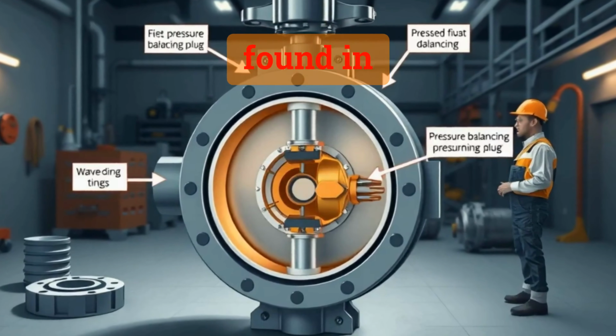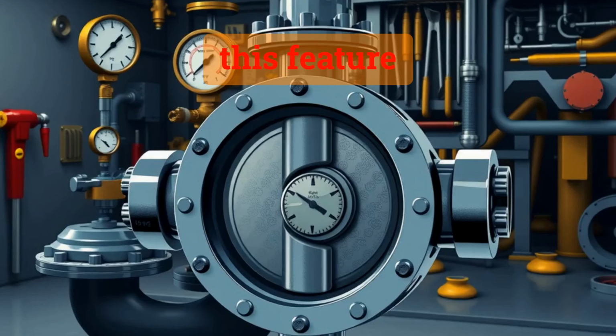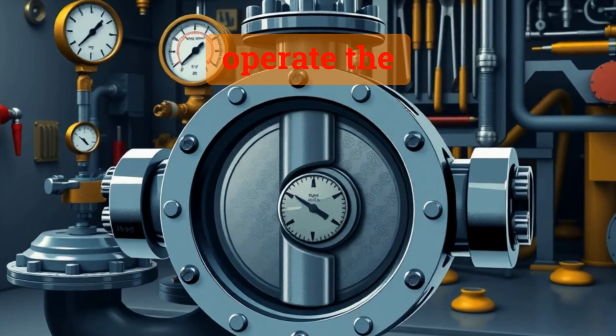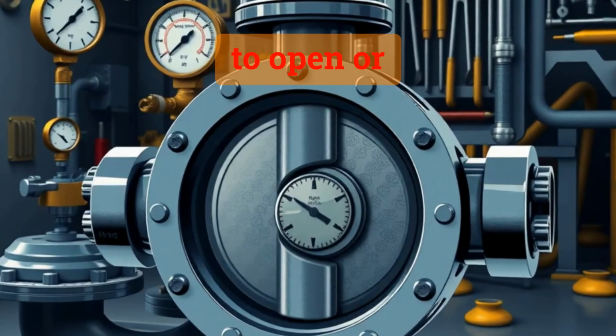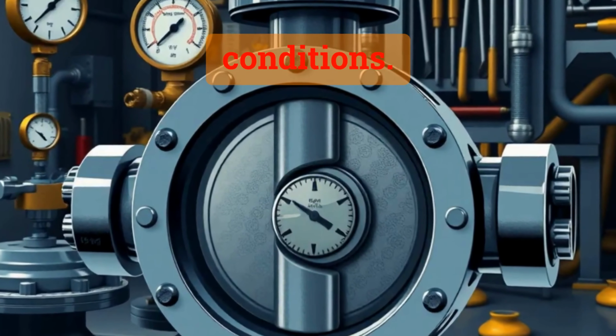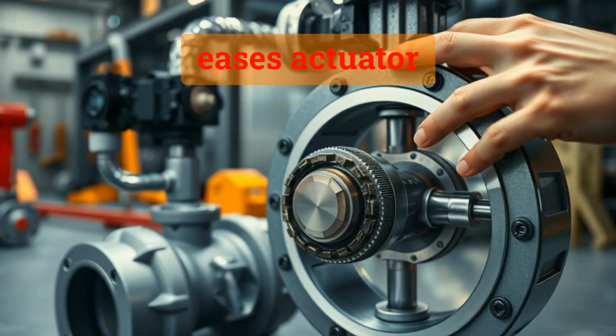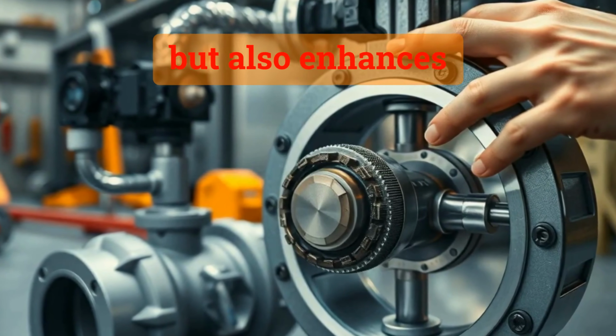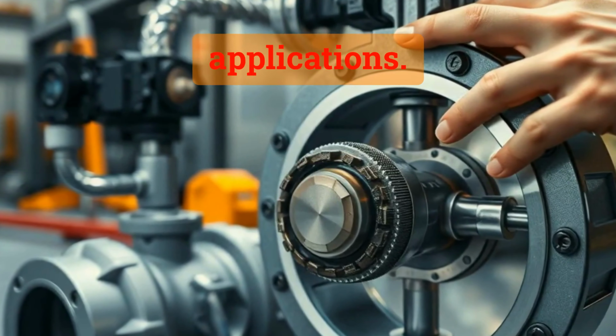A pressure balancing plug is a specialized design element found in globe valves. By equalizing pressure across the valve plug, this feature reduces the force required to operate the valve, making it easier to open or close under high-pressure conditions. This not only eases actuator load, but also enhances control accuracy in throttling applications.